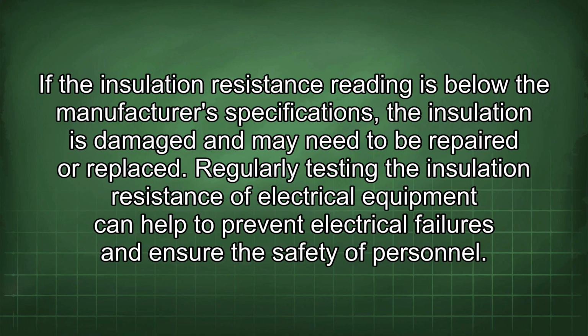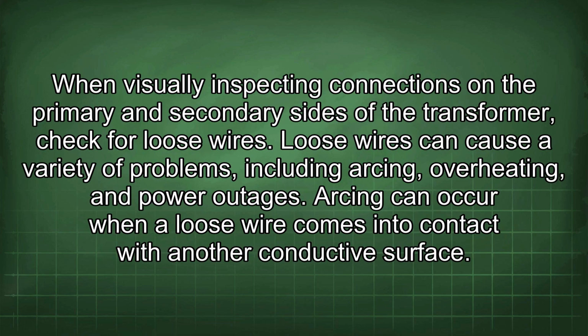If the insulation resistance reading is below the manufacturer's specifications, the insulation is damaged and may need to be repaired or replaced. Regularly testing the insulation resistance of electrical equipment can help to prevent electrical failures and ensure the safety of personnel. When visually inspecting connections on the primary and secondary sides of the transformer, check for loose wires.